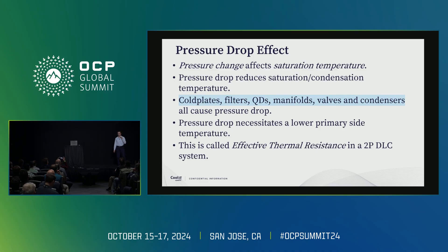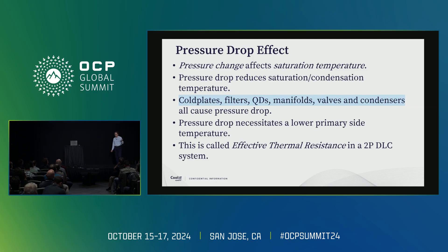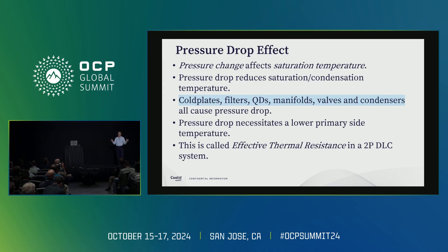One of the most important and most challenging design factors in two-phase systems is pressure drop. Pressure drop is inevitable — you cannot have zero pressure drop. There will be cold plates, quick disconnects, filters, manifolds, and valves, all with pressure drop. In two-phase, the pressure drop affects your saturation temperature and condensation temperature, which reduces the system-level performance compared to single phase. In single phase, if you have a pressure drop, you just need a higher pump to recover it. But in two-phase, pressure drop is tied directly to the saturation temperature, and that has a very important effect.